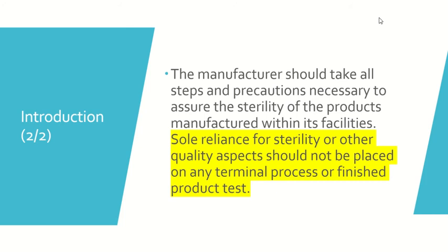Sole reliance for sterility or other quality aspects should not be placed on the terminal process or the finished product testing, right? So it does not matter whether your process is terminal and you're going to kill all the microorganisms at the end of your sterilization process, or you have a very extensive testing process from each and every phase of your manufacturing or filling. That does not make sense. You cannot demonstrate a good design or good control through this process.